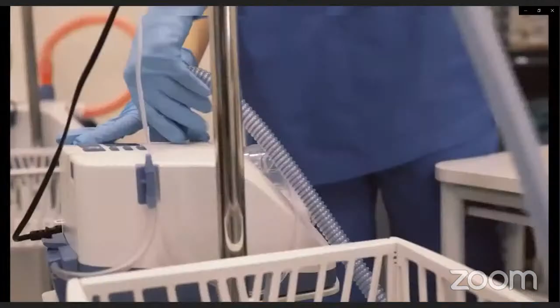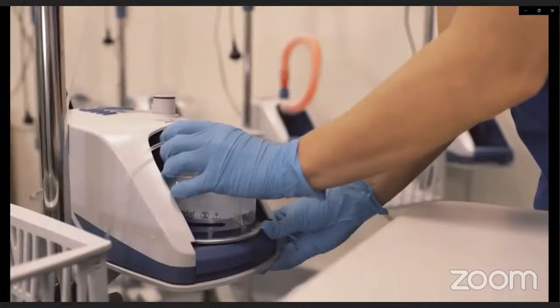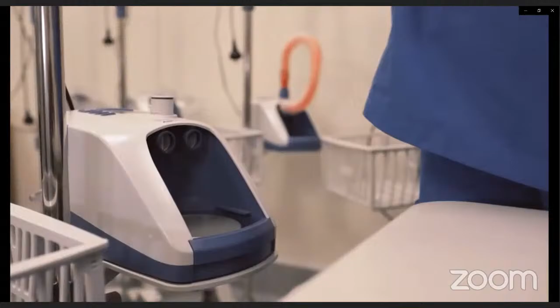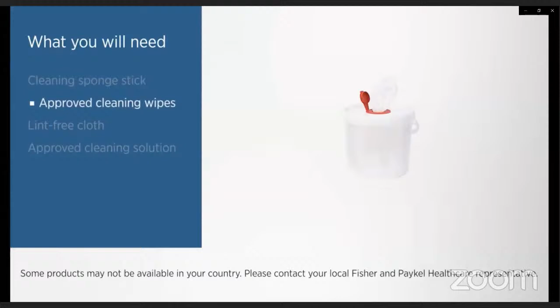Switch off the unit and unplug it from the mains utility power socket. Remove the breathing tube, water chamber and water bag and safely dispose of them. For cleaning, you will need a cleaning sponge stick, approved cleaning wipes, a clean, damp, lint-free cloth, and an approved cleaning solution.